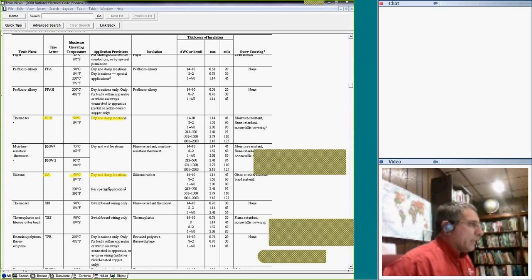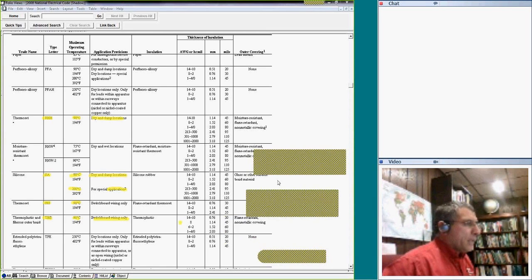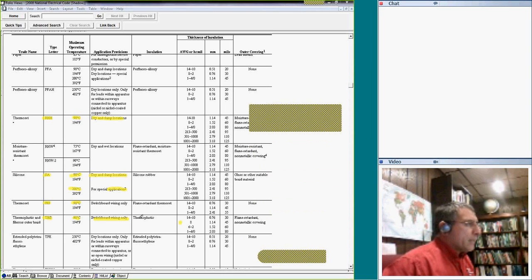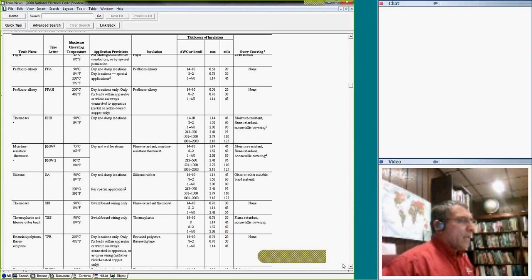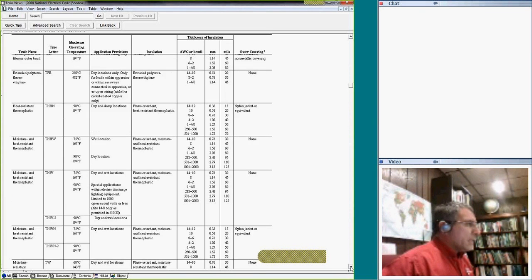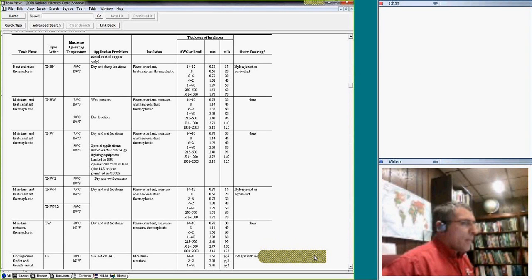Special, I can't use it in a wet location. It can be rated as high as 200. SIS cable is rated for 90 degrees. TBS is rated for 90 degrees, which is switchboard wiring. This tells you what the insulation type is, the size you can buy it in, the circular mil area, as well as the outer covering if it has any. These are the most important cables that you're going to encounter in your career.